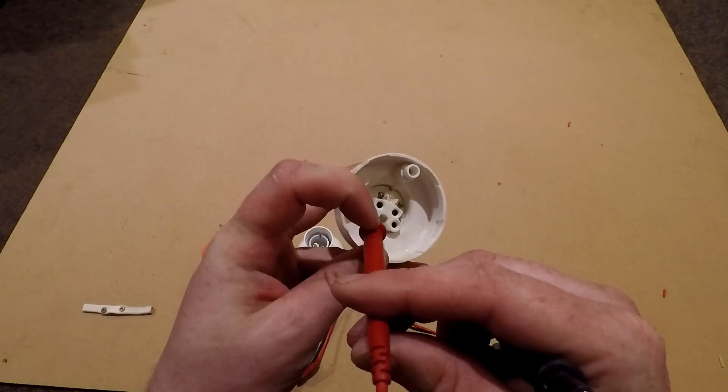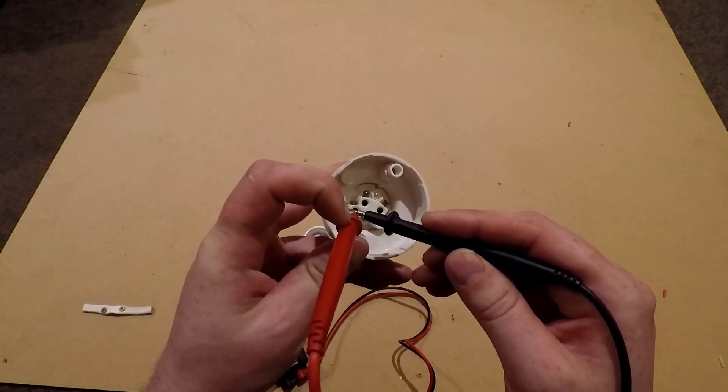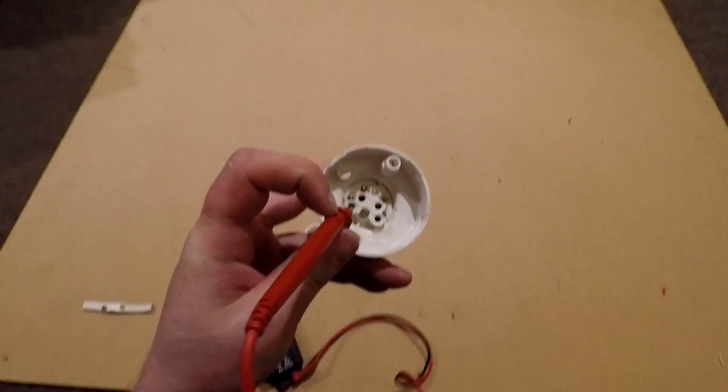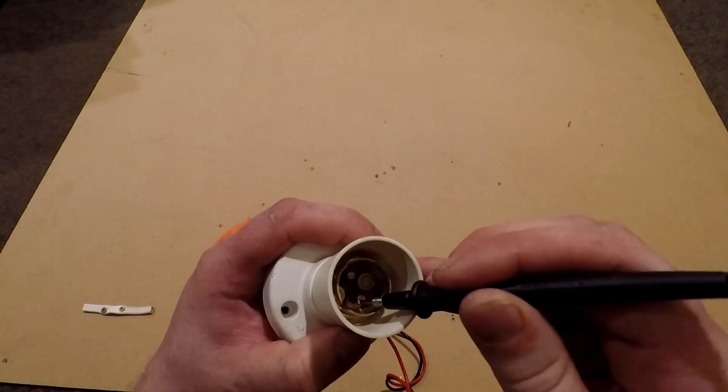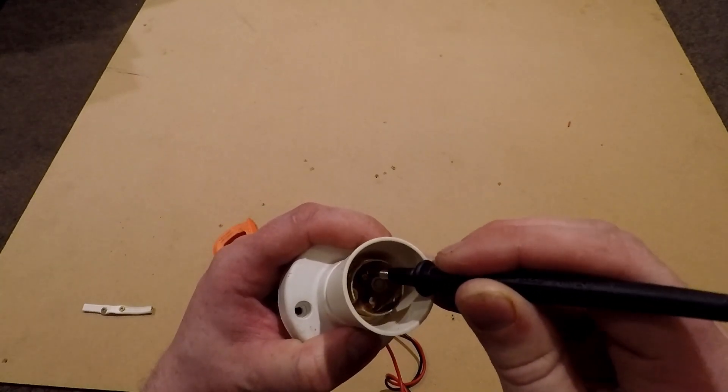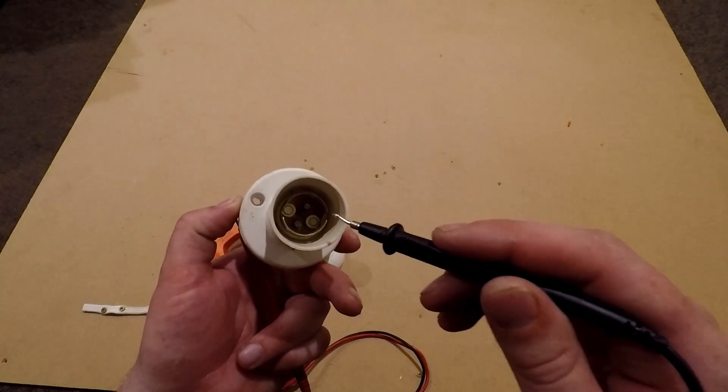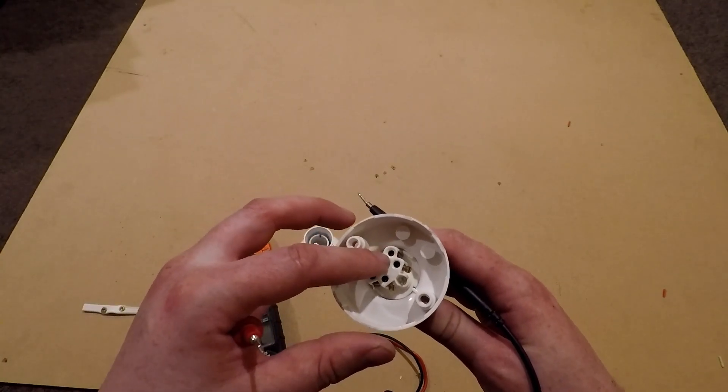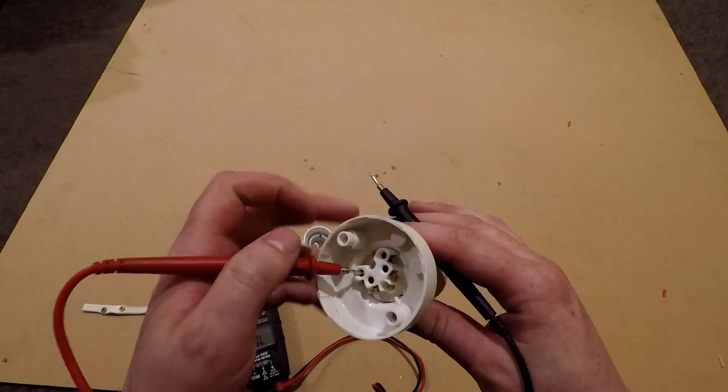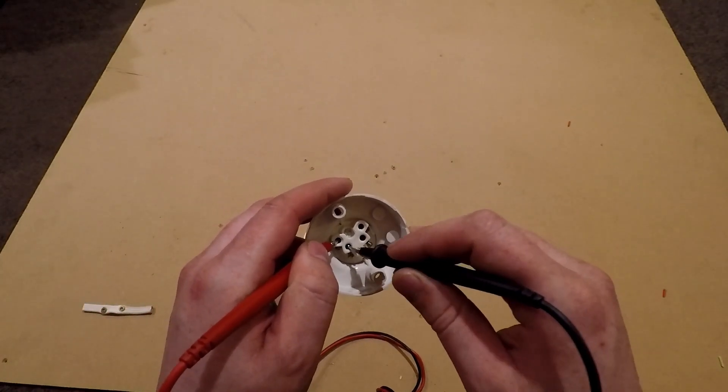Now on the back of these, put one end into any terminal, test the others. If it doesn't beep like that then it's not linked into them. And then holding it in that same terminal you want to touch it on the brass pins inside these fittings. Because the terminal hasn't beeped on any of these pins, metallic parts, or other terminals, it is a loop terminal and it is isolated to itself. Therefore it can be used like a connector, and we can prove that with the other one as well. So we've tested these two back terminals and they are loop terminals as suggested.